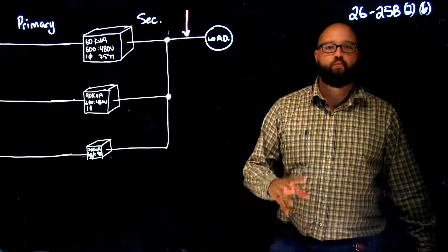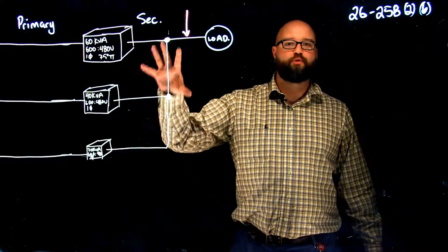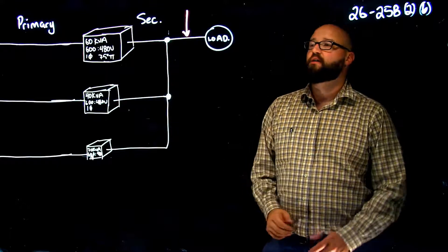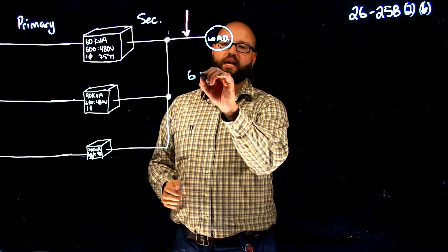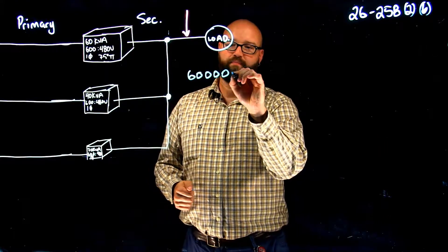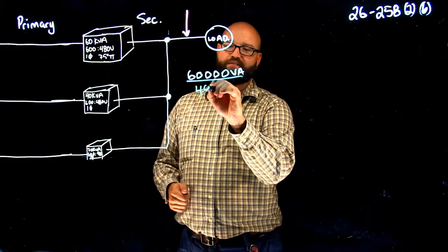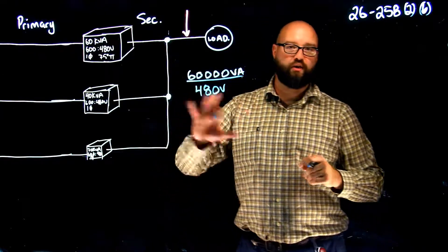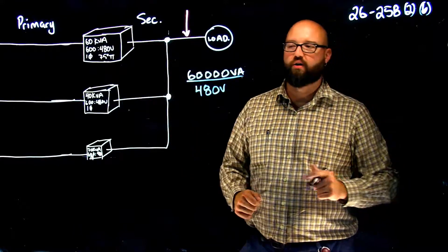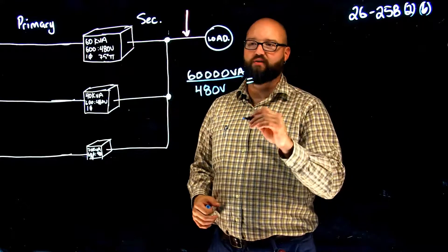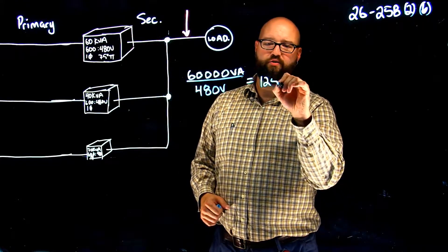So first thing we need to figure out what is the rated secondary current of each one of these transformers. We're not going to worry about the primary, just the secondary. So our first one we have our 60 kVA divided by my secondary voltage of 480 volts, and again we do not need to use the root 3, it's just single phase calculation, gives us a rated secondary current on our 60 kVA of 125 amps.